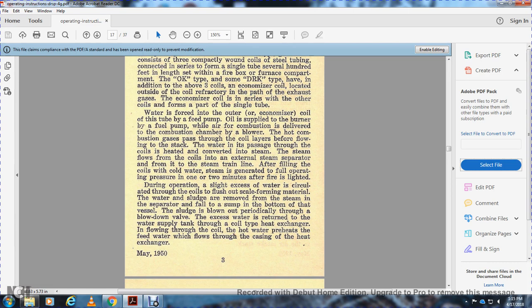Water is forced into the economizer coil by the feed pump, and oil is supplied to the burner by the fuel pump, while the air for combustion is delivered into the combustion chamber by the blower. The hot combustion gas passes through the coil layers before flowing into the stack. The water passes through the coils, is heated, and is converted into steam. The steam flows from the coils into the external steam separator and from it to the steam train line. After filling the coils with cold water, steam is generated at full operating pressure 1 to 2 minutes after the fire is lit.